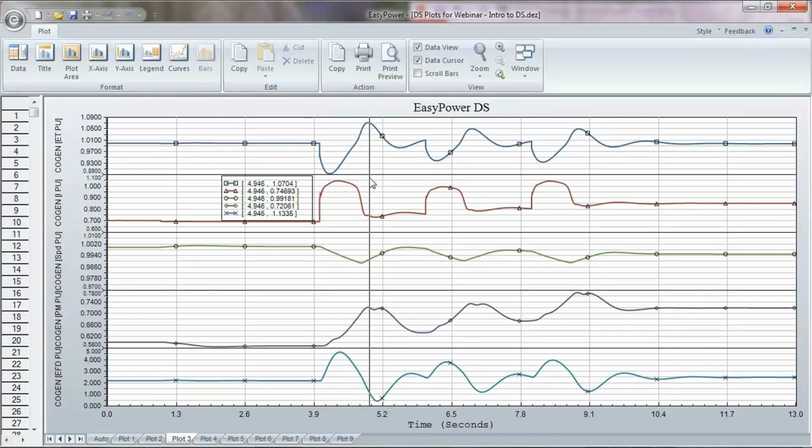I've seen these voltage responses show up on the bridge, on the 120 volt outlet, because some large motor was starting over and over and over again. Instead of putting it on a drive and controlling its flow, it's on a start. They start it, then stop it, then start it, then stop it. I saw that happen repeatedly up there on the bridge. But this was affecting every power outlet, everything on the whole ship.